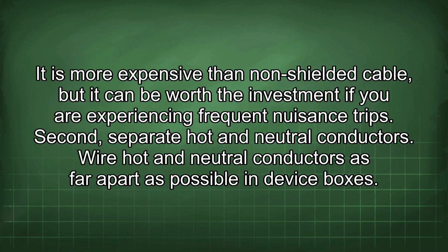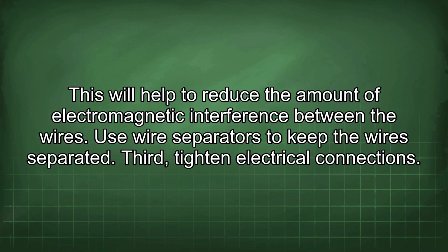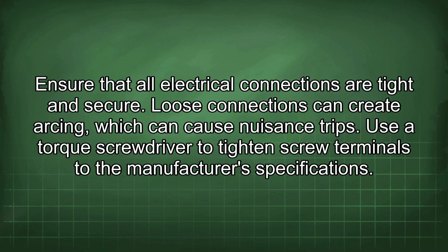Wire hot and neutral conductors as far apart as possible in device boxes. This will help to reduce the amount of electromagnetic interference between the wires. Use wire separators to keep the wires separated. Third, tighten electrical connections. Ensure that all electrical connections are tight and secure. Loose connections can create arcing, which can cause nuisance trips. Use a torque screwdriver to tighten screw terminals to the manufacturer's specifications.